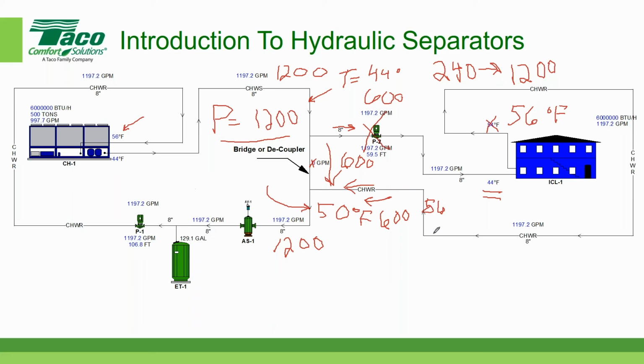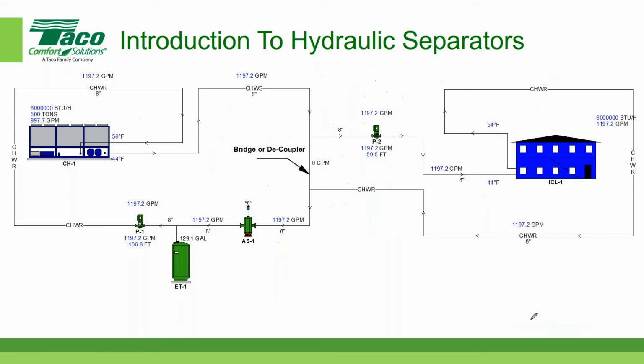Okay, so let's look at another case. Erase some of these lines, too many lines in there. So now, we had the primary flow equal to the secondary flow. We had the primary flow greater than the secondary flow. What would happen if the secondary flow was greater than the primary flow? Well, let's see what happens. Again, the primary flow is still 1,200 gallons per minute. And let's say, for some unknown reason, we don't have to worry about it so much right now, that the secondary flow is 1,800 gallons per minute.